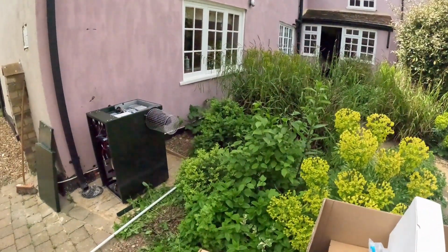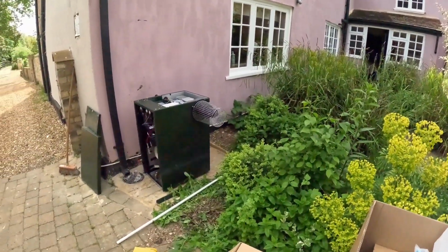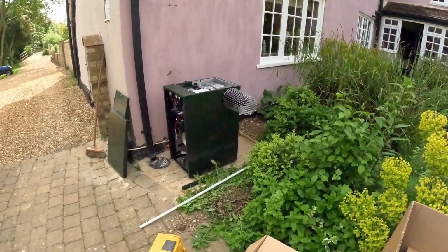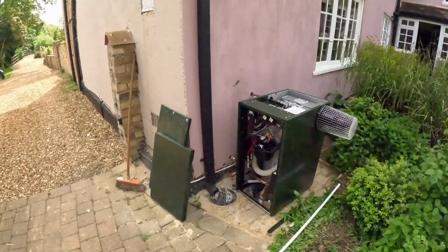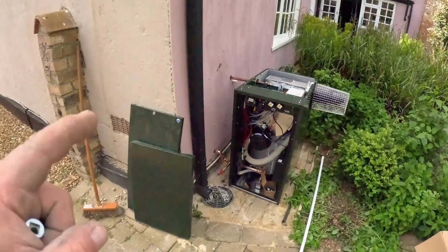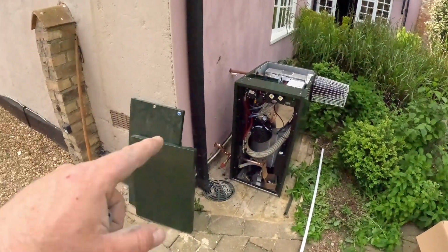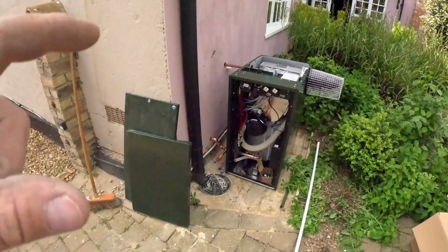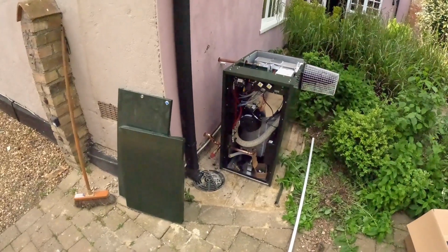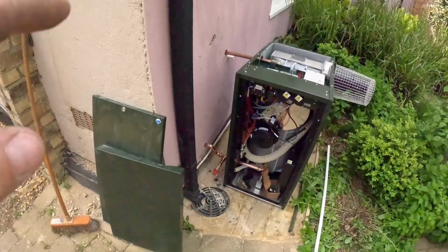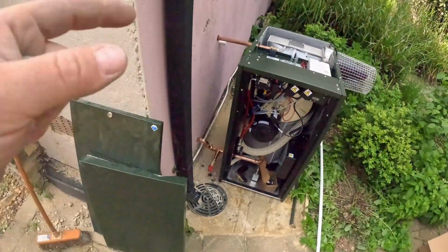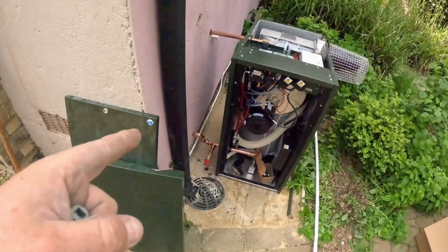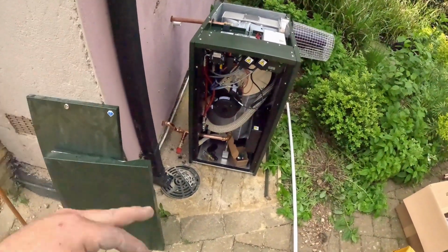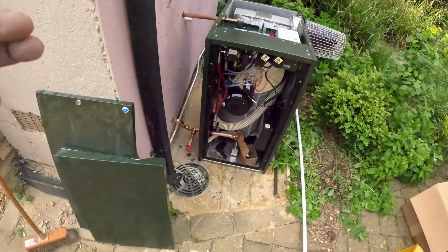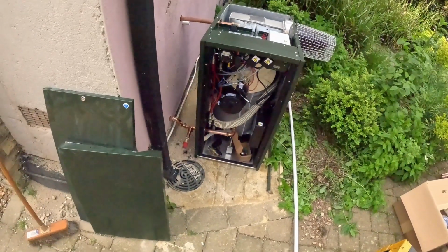So that's another job for another day, to run another oil line for the Aga, but we'll do that just before September when they normally turn them on, so we can give it a good service then too. You shouldn't have a combined oil line for your boiler and Aga or anything else on a vaporising unit. We're going to get an oil filter down there since there's no filters really - a 90-degree fire valve, bring the oil line in, condense will come straight out there, and again we'll lag that with 25mm external rated lagging.